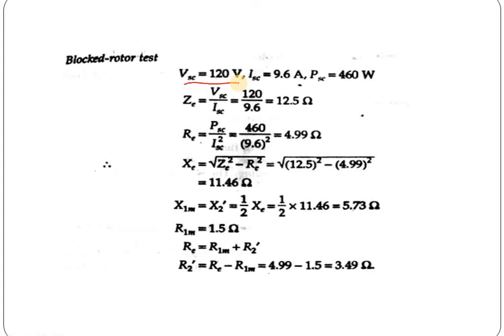From the voltmeter reading and ammeter reading, by using Ohm's law, we can get the value of equivalent circuit impedance ZE, which is VSC divided by ISC. We are getting the equivalent impedance value as 12.5 ohm. Now, equivalent resistance can be calculated using the formula P equals I squared R. From there, RE equals PSC divided by ISC squared.